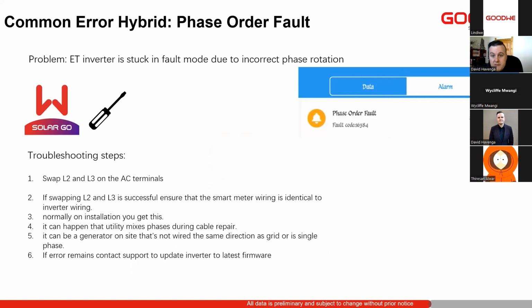So then with the three-phase devices, after installation, sometimes we can have the devices stuck in a fault mode. Because we didn't do the installation of the three-phase inverter, I thought it's very important to cover this. So the most common reason for that inverter not to connect to the grid and remain in a fault mode will be phase order fault. The inverter always checks the phase rotation, so it always has to have a right-hand phase rotation.